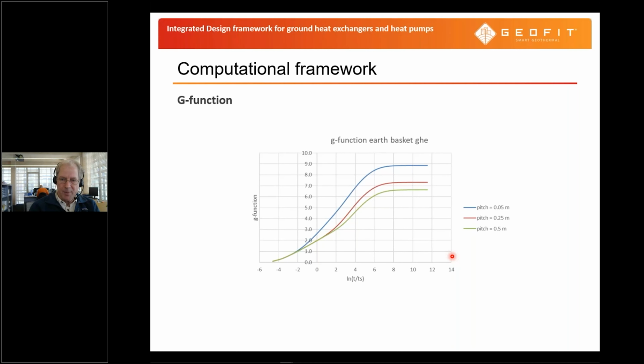This can take a long time, as you can imagine. So the basic idea here is that we can do this for only one step change in energy demand, and then calculate the typical response for the whole heat exchanger system. And this typical response is translated to what's called a G function. And then with the G function, we do not have to do all the detailed calculations with the analytical equation, but we can very quickly calculate the response of the system over the whole time period.